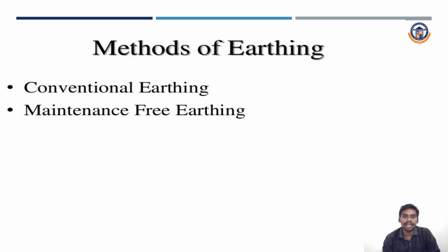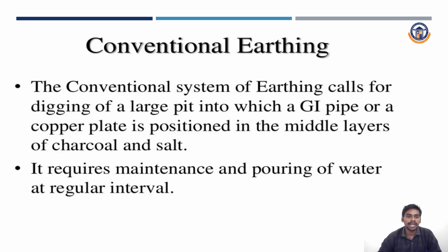Two types of earthing are available: the conventional earthing, and the maintenance free earthing. First, conventional earthing. The conventional system of earthing calls for digging a large pit into which a galvanized iron pipe or a copper plate is positioned in the middle layers of charcoal and salt. We use charcoal and salt to retain the moisture level for a long period. It requires maintenance and pouring of water at regular intervals.